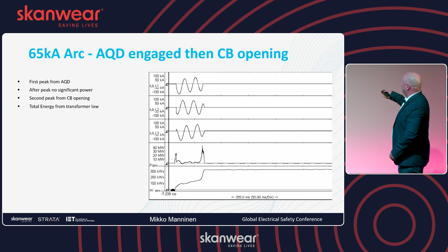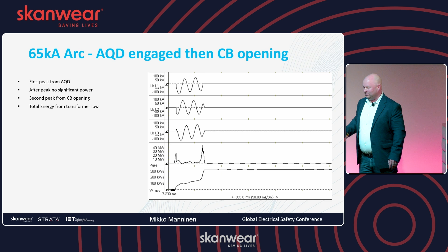Did you know that actually you have two arc flashes here? You have the arc flash and you have the circuit breaker arc flash. Always when you open the breaker, you have an arc flash. That's how it goes. This is more than double the amount of current, 65 kiloamps. This is how it looks from the transformer end when the arc quenching closes. The first peak here is the arc quenching closing and absorbing all the current. So this is when we have already mitigated the fault. The actual fault has already been shut down. And what is the next peak? It's the breaker opening. So there will be another peak, and the total accumulated energy is 300 kilowatts in this fault.